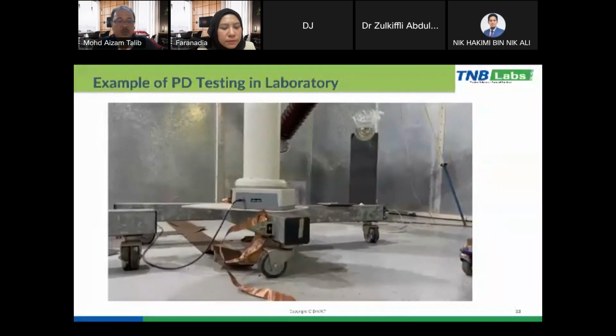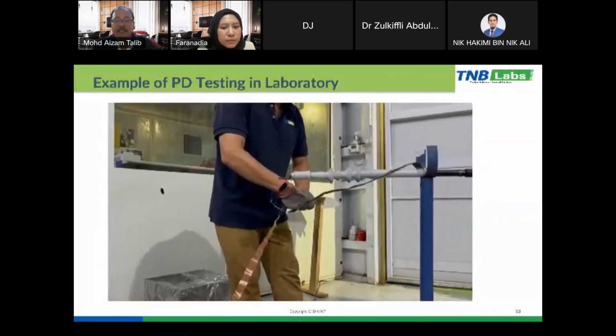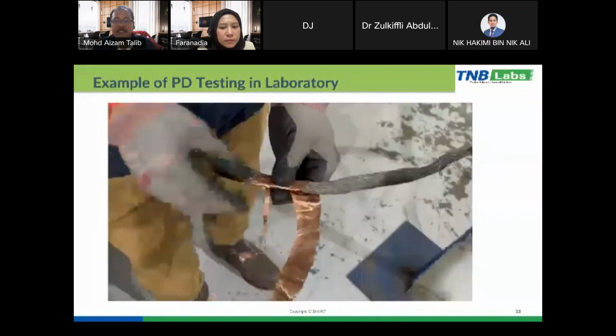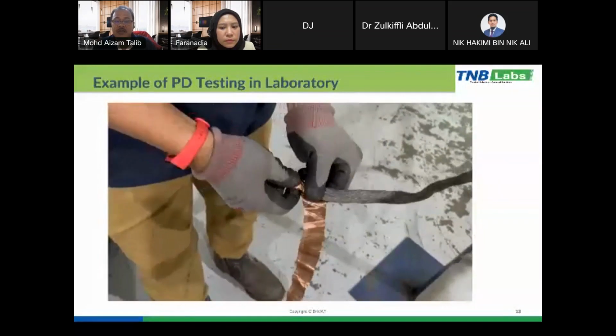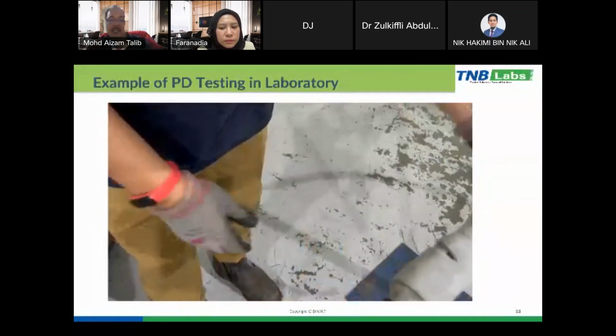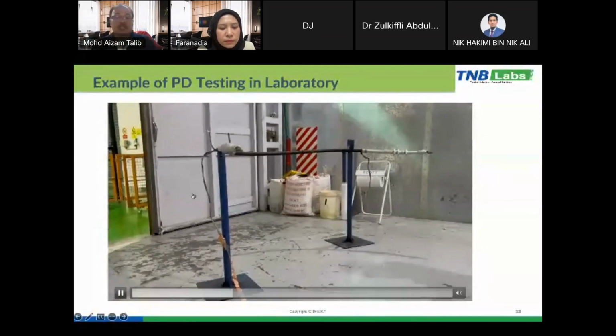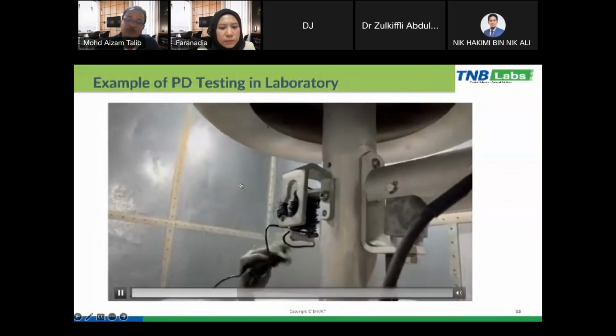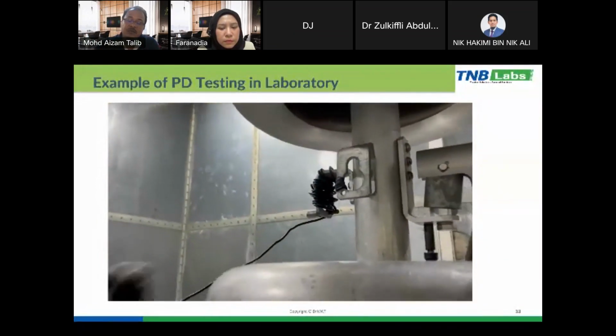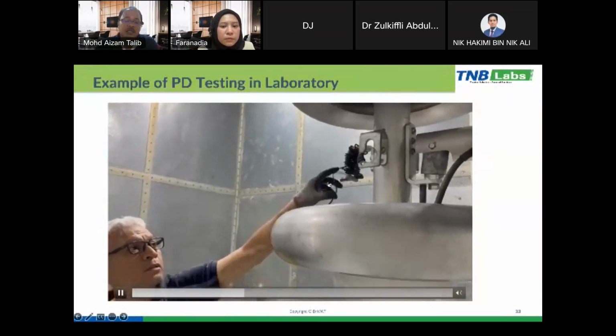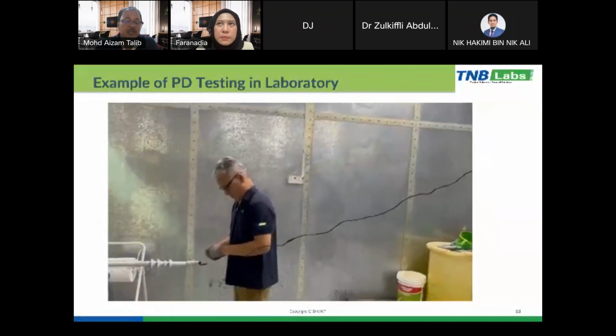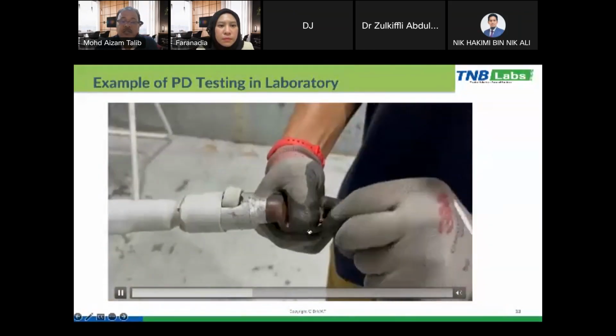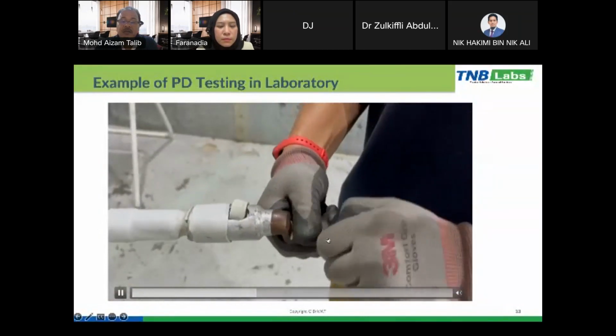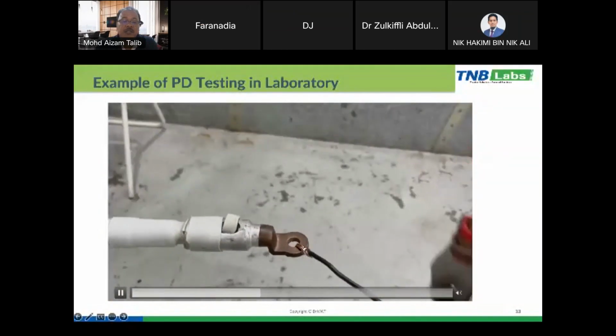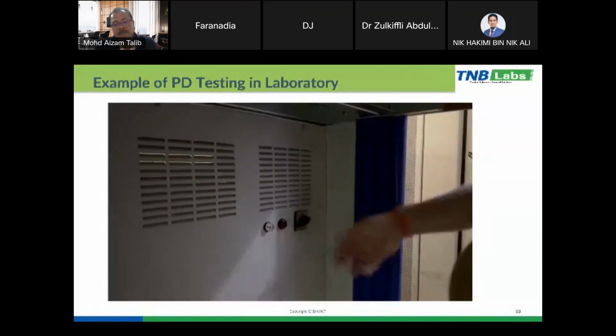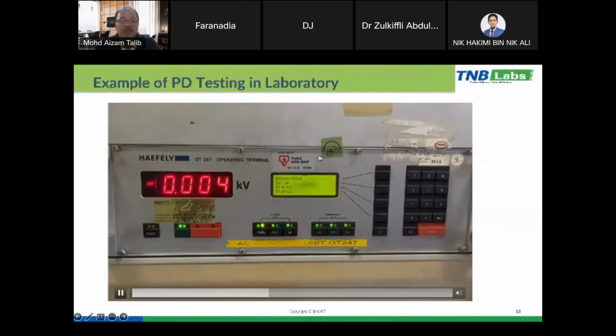So we need to have good, proper grounding. Otherwise, we will have partial discharge not caused by a void in the insulation, but due to improper grounding. So the other terminal we put to the ground, and then we connect the HV source to the cable conductor. So our foreman connects the HV source to the cable conductor here. Then we turn on our HV source. Okay.